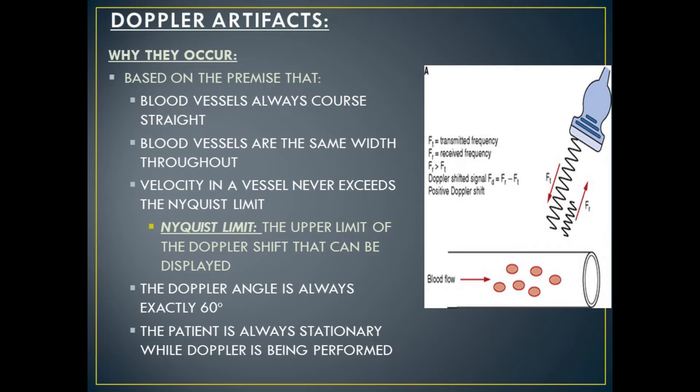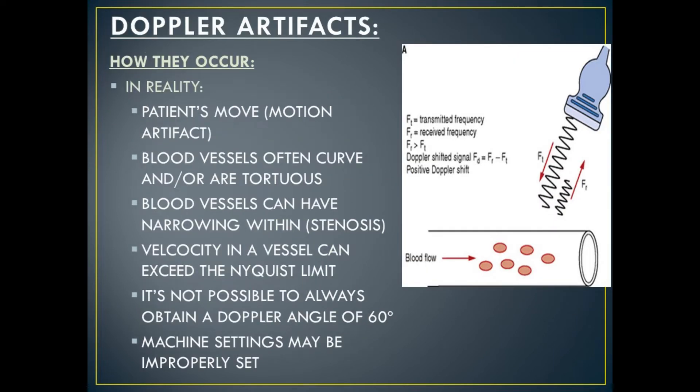Doppler artifacts occur based on the premise that blood vessels always course in a straight line, blood vessels are the same width throughout, and velocity in a vessel never exceeds the Nyquist limit. The Nyquist limit is the upper limit of the Doppler shift that can be displayed by the ultrasound machine. Doppler artifacts also occur based on the premise that the Doppler angle is always exactly 60 degrees, and the patient is always stationary while Doppler is being performed. In reality, Doppler artifacts occur because patients move (known as motion artifact), blood vessels often curve or are tortuous, blood vessels can have narrowing within them (known as stenosis), velocity in a vessel can exceed the Nyquist limit, it's not possible to always obtain a Doppler angle of 60 degrees, and machine settings may be improperly set.